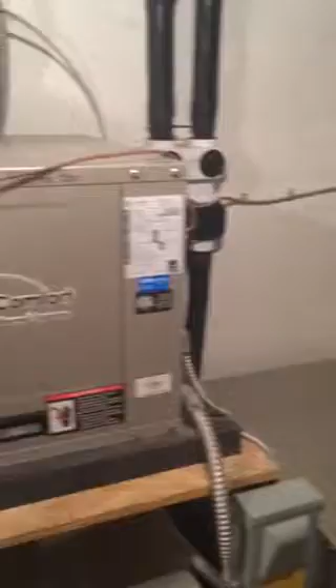I'm ordering 2 pumps, and I'd really like to pipe them both in and just run one at a time. Both variable speed pumps each have the capacity to do the job, but I only need to run one at a time. Each unit's geo lines have a solenoid on it, and when that's calling, it opens up that valve and feeds that zone. The variable speed pump is controlled by pressure: if one is calling, it'll turn at a certain speed; if all of them are calling, it'll turn to a much higher speed, so it's maintaining constant pressure.